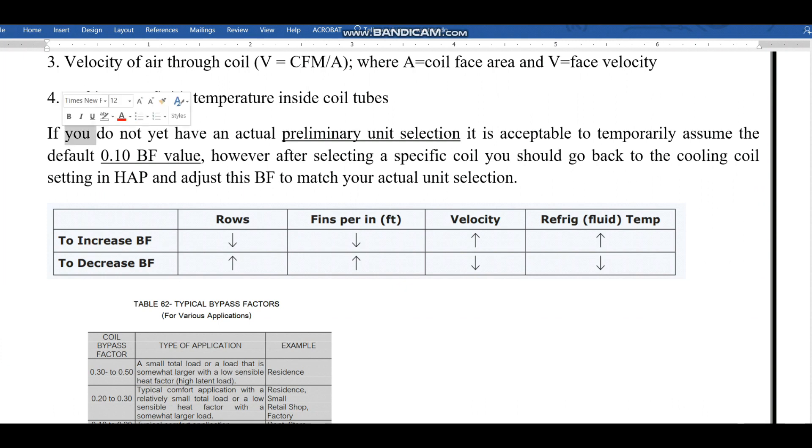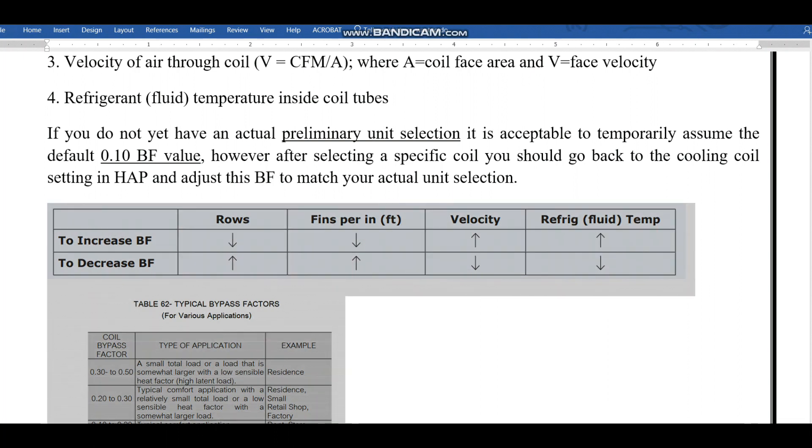Normally what we are doing in the project: if you don't yet have an actual preliminary unit selection at the starting stage of the project, then it is acceptable to temporarily assume the default 0.1, that means 10 percent, as a bypass factor value. However, after selecting the specific coil, you should go back to the cooling coil setting in HAP and adjust the bypass factor to match your actual unit selection.